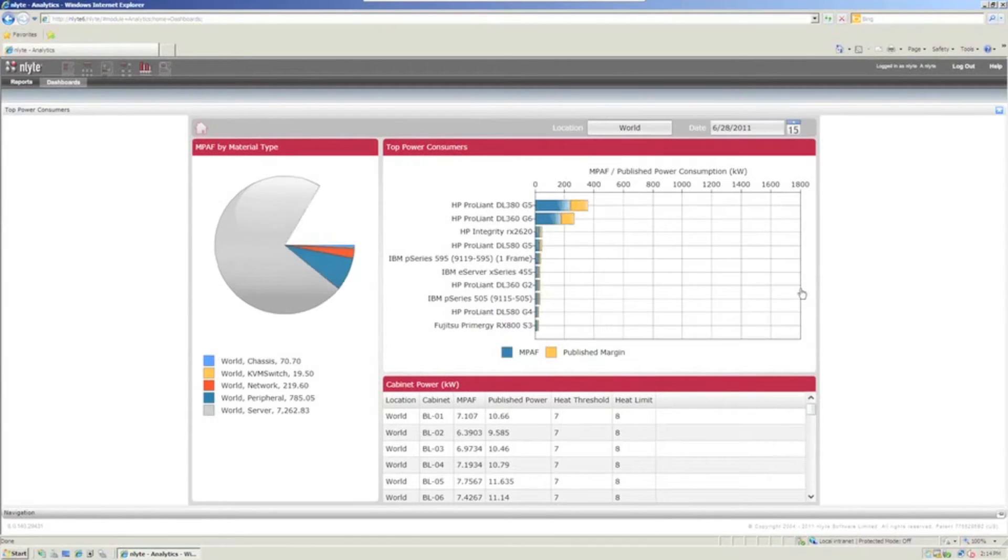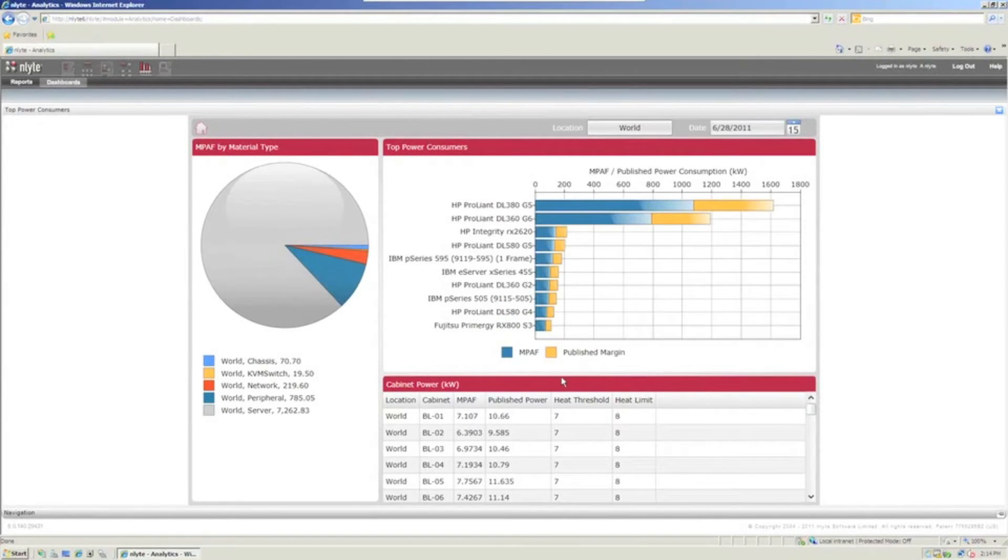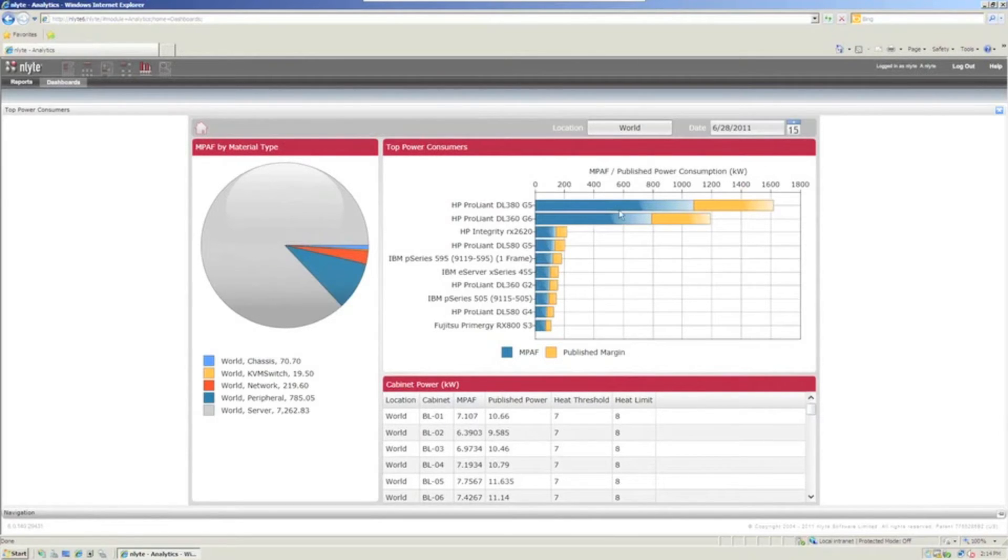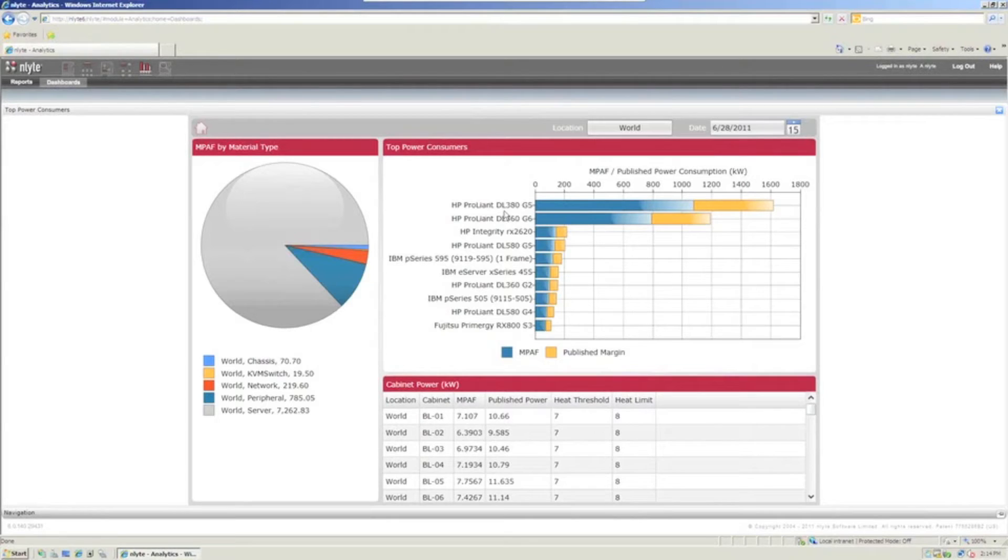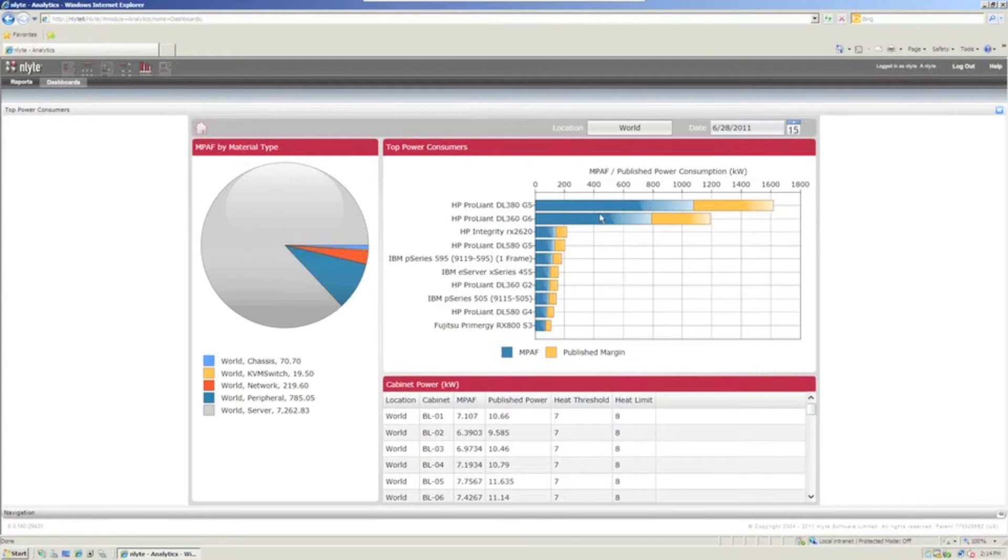But then we can also drill down further into that to look at, well, what are the top power consumers, right? If you've got a green initiative going on, you probably want to look at things like this. And what immediately probably jumps to you is look at the amount of power being used by these older HP devices up here. That would tell me as a data center manager that we should probably start thinking about a migration plan to replace these very power inefficient servers with something that's a little bit more green by today's standards.